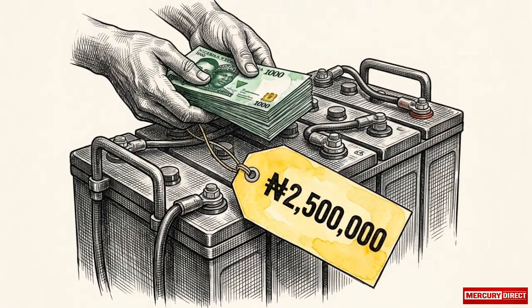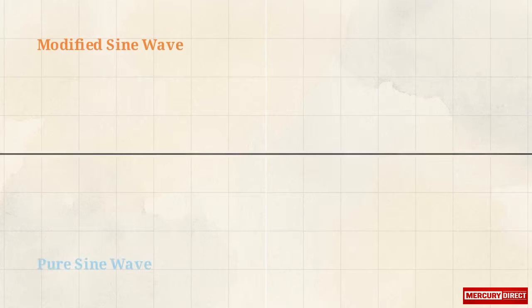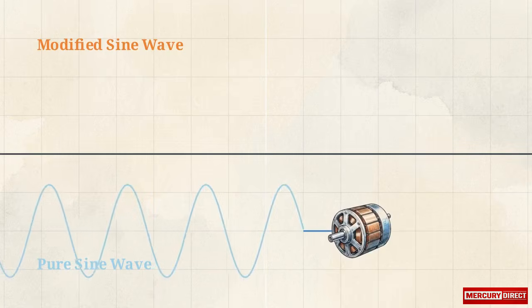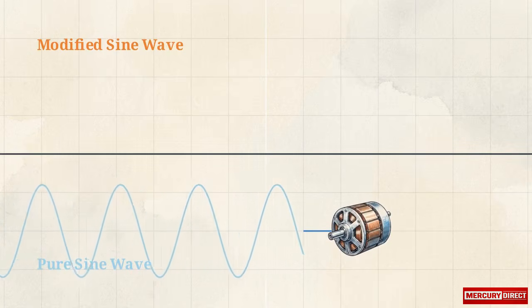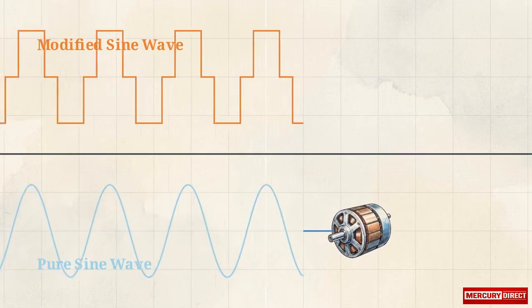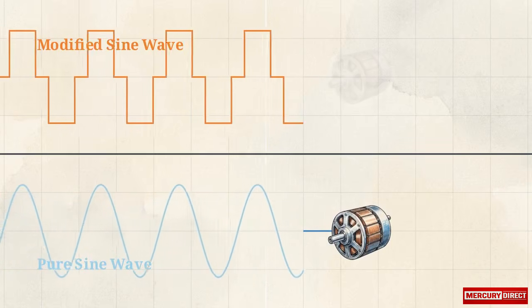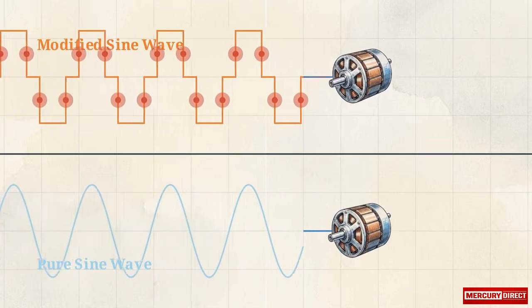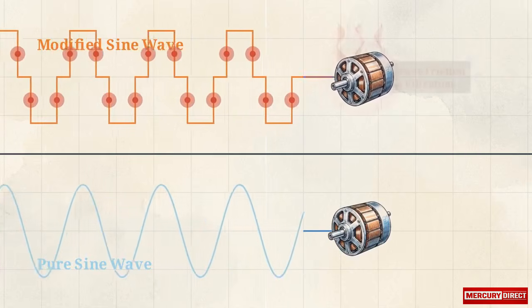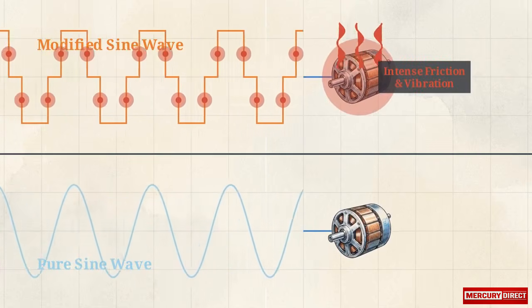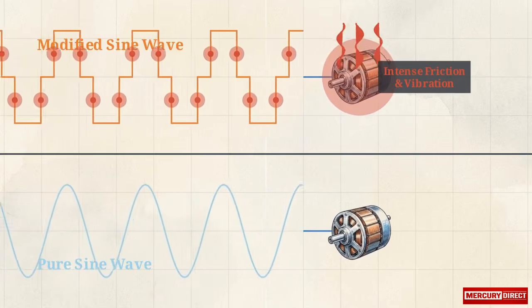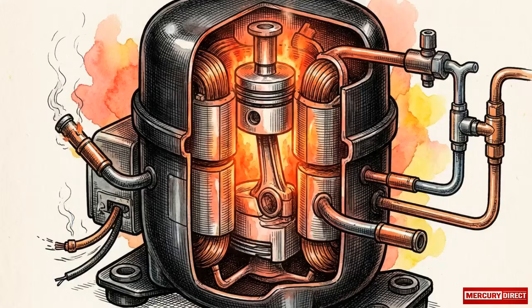Facing that massive hardware cost, many people try to save cash by purchasing a cheaper, modified sine wave inverter. This split-screen diagram illustrates why that fails. Grid electricity is a smooth, continuous curve, like the pure sine wave on the bottom. Modified inverters produce the jagged, stepped power wave on the top. When you feed a compressor those sharp, blocky electrical pulses, the motor is forced to fight itself. The physical result is intense internal friction and violent vibration. The compressor runs dangerously hot, consumes extra power, and will eventually burn out entirely.